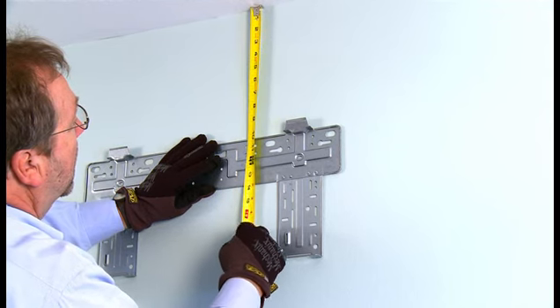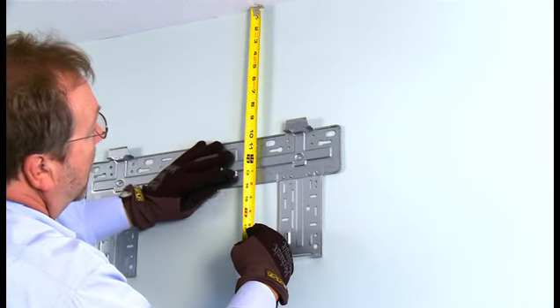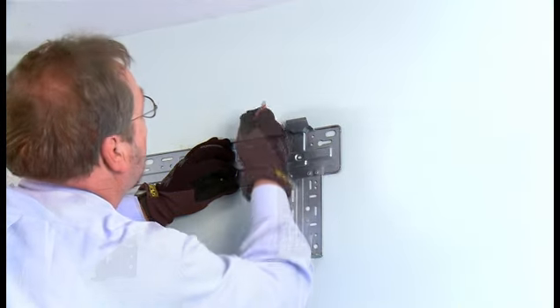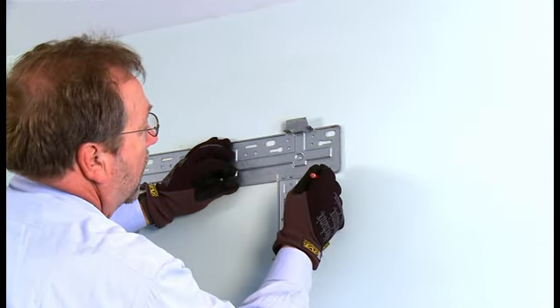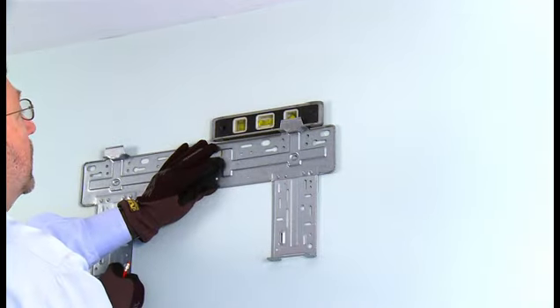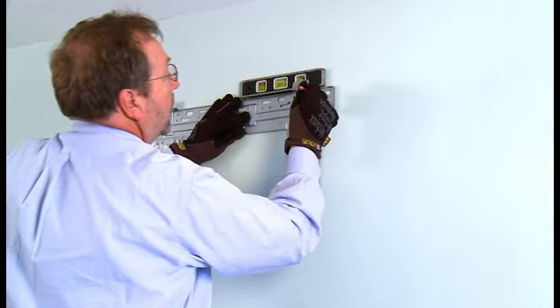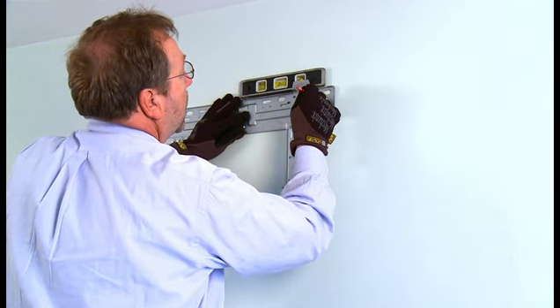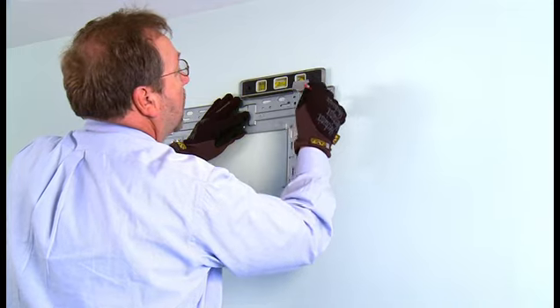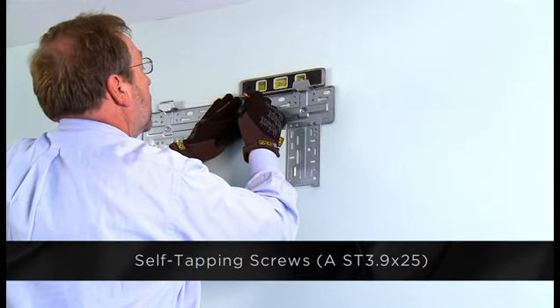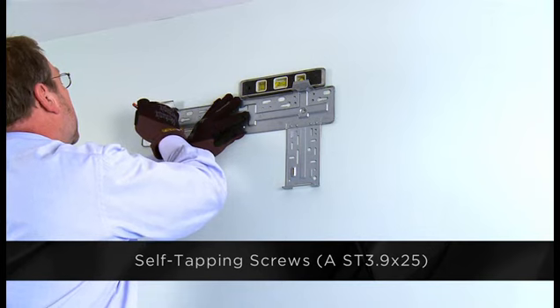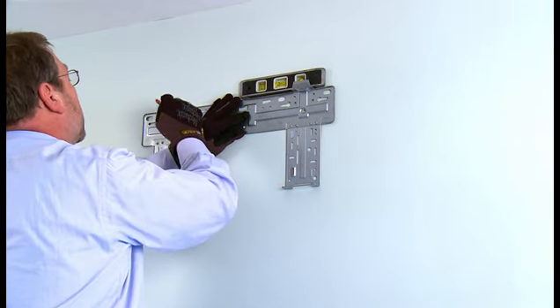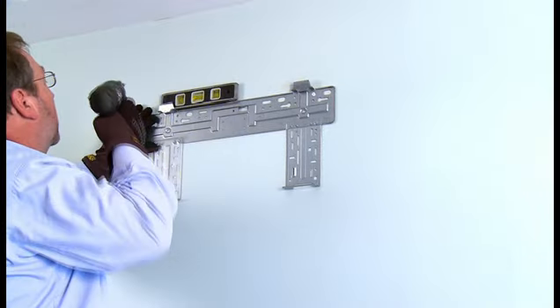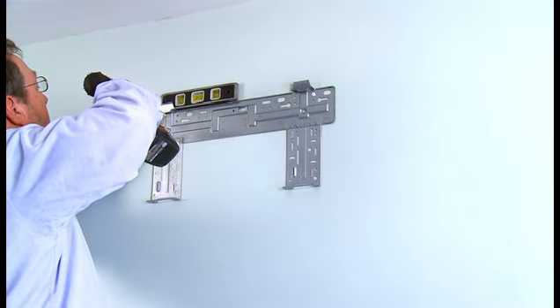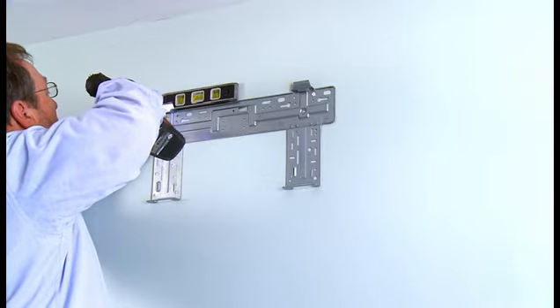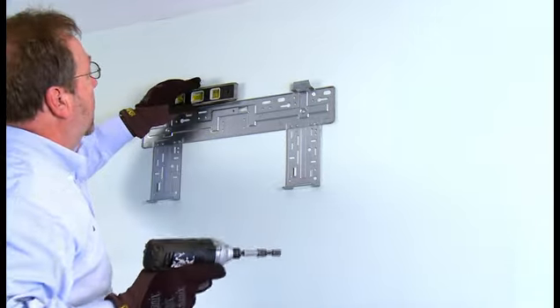Select a wall location that's at least 6 inches from the ceiling. There must be at least 6 inches of clearance on either side of the unit. The installation plate will be attached to the interior wall in a horizontal position. Make sure the installation plate is level. Locate the mounting points in the installation plate. We recommend the placement of screws correspond with the wall's structural components. Using the self-tapping screws packaged with the unit, install the installation plate. Again, use the level to check for accuracy. Tiled, concrete, or walls of similar composition require anchor supports and the appropriate type of assembly screws. Note the installation plate must be flush with the wall.